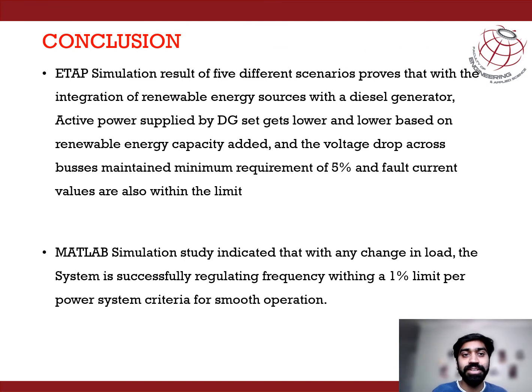So to conclude our presentation, for the first part of this project, we have done the ETAP simulation with 5 different scenarios with the integration of renewable energy sources with the current diesel generation and wind generation facility in Ramea Island. Active power supplied by the DG sets gets lower and lower based on the renewable capacity added, the voltage drop across the bus is maintained within the minimum requirement of 5%, and the fault current level is also within the limit. And in the second part of our project, we simulated the frequency deviation with the droop control method, and we observed that frequency regulation can be achieved within the 1% limit with the increase of renewable sources such as pumped hydro and V2G, with the current existing facilities in Ramea Island.